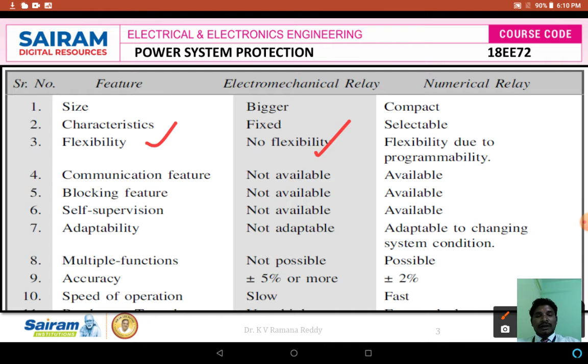Whenever the line current or line voltage exceeds that predetermined value or setting value, it automatically turns into an abnormal condition. Therefore it is going to convert that raw data into suitable data, and we can convert that raw information to suitable information, and we can do a lot of analysis, and we can identify more problems and fault severity with respect to time, temperature, current, voltage, phase angle. All this information we can easily get through a numerical relay.